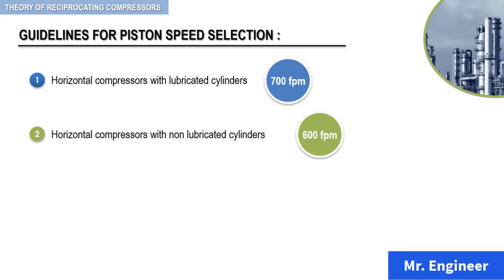For vertical compressors with lubricated cylinders, you can use 800 feet per minute.